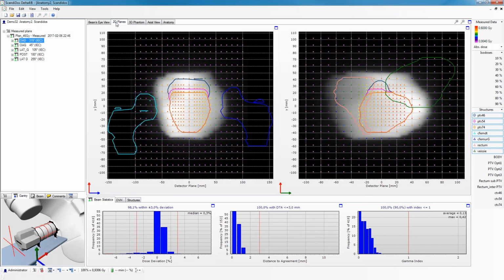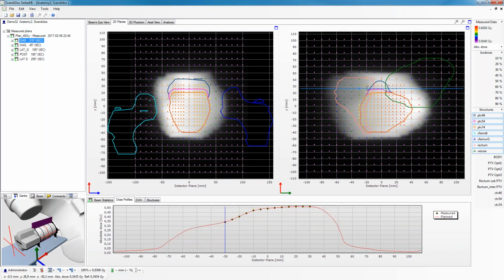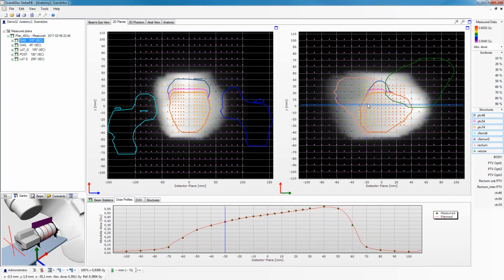The tab 2D planes is just looking at the two detector boards mounted inside the phantom, just as if I would have dismounted them from the phantom and put them in front of me. So I can see that I have the horizontal and the vertical detector board. If I right click on any of them, I can show profiles over the dose distribution. You can see that I get a nice profile here where the dots are representing measured dose, and the line is representing the planned dose.